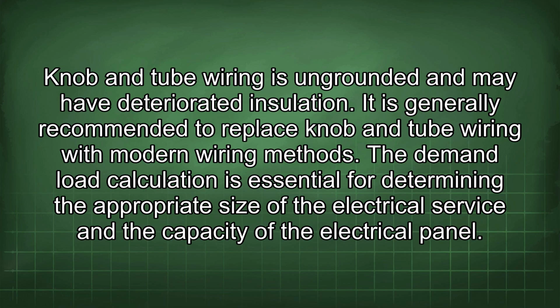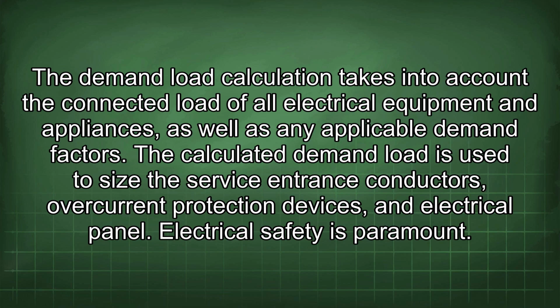The demand load calculation is essential for determining the appropriate size of the electrical service and the capacity of the electrical panel. The demand load calculation takes into account the connected load of all electrical equipment and appliances, as well as any applicable demand factors. The calculated demand load is used to size the service entrance conductors, overcurrent protection devices, and electrical panel.